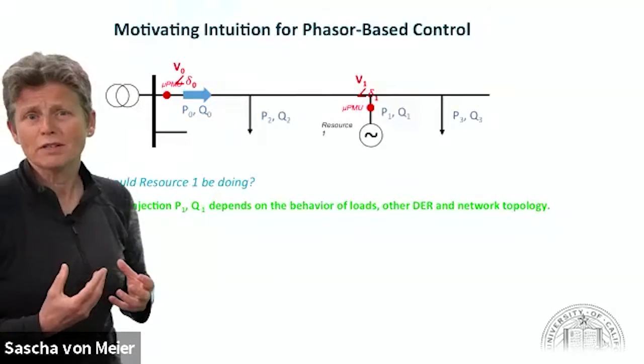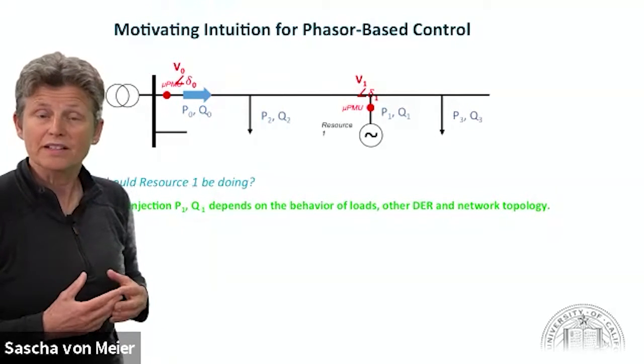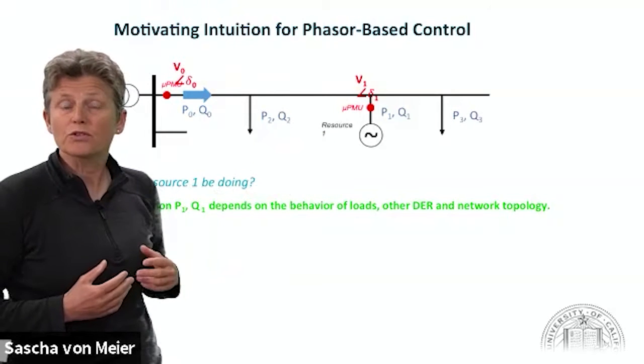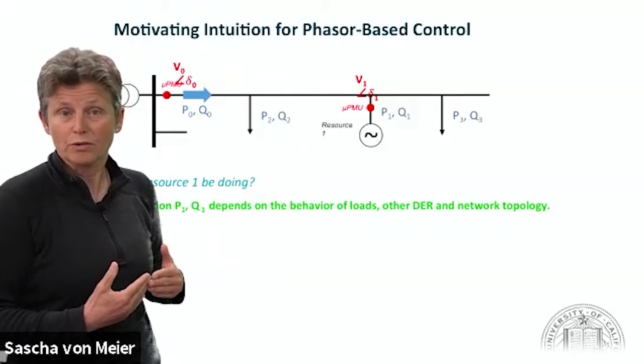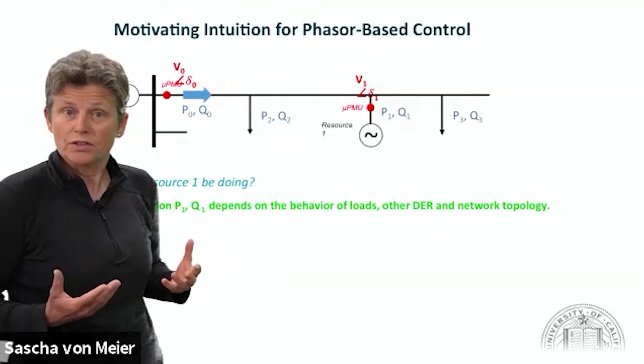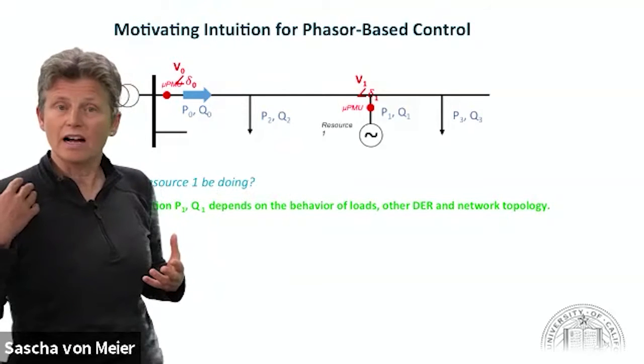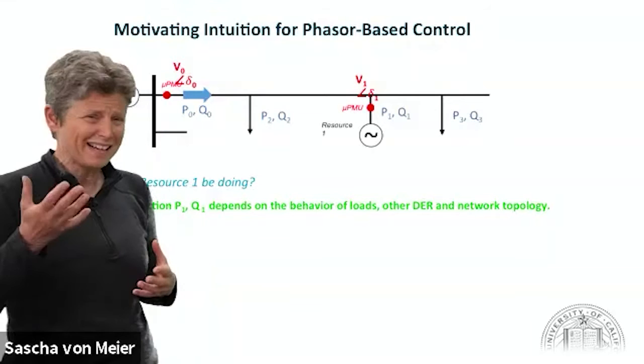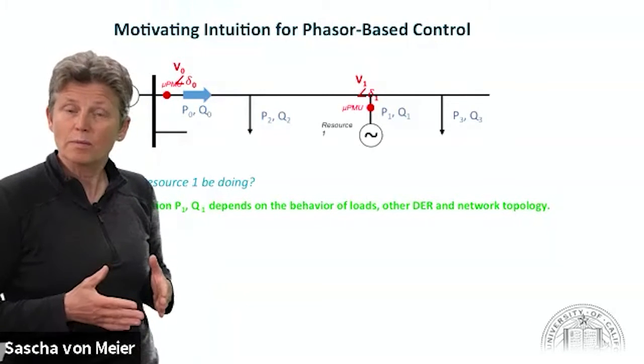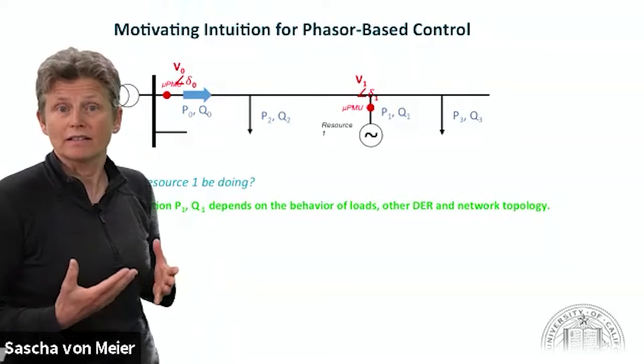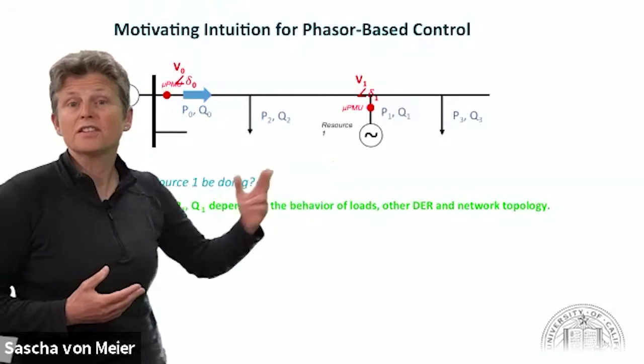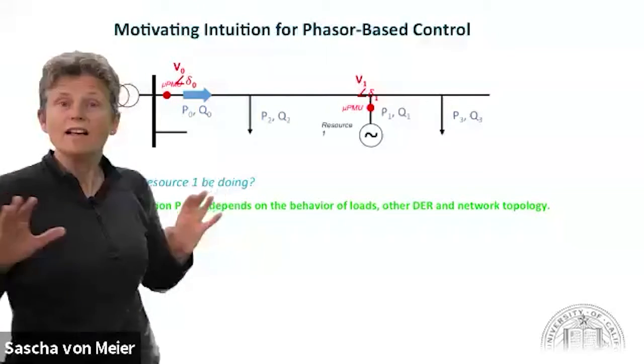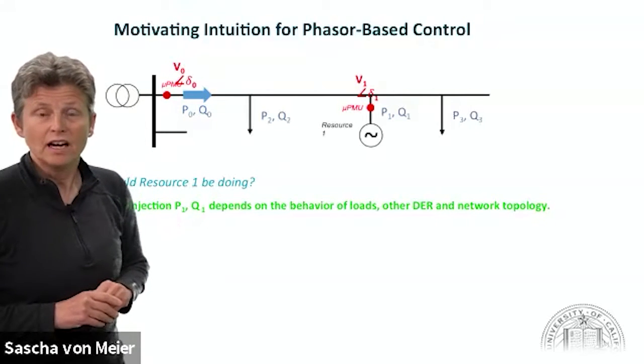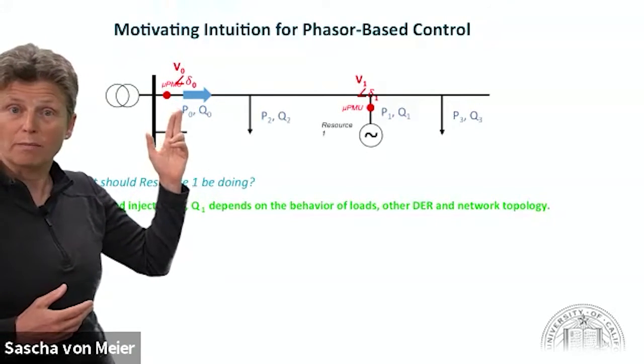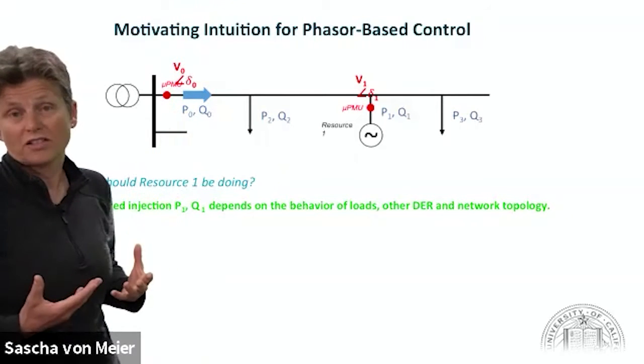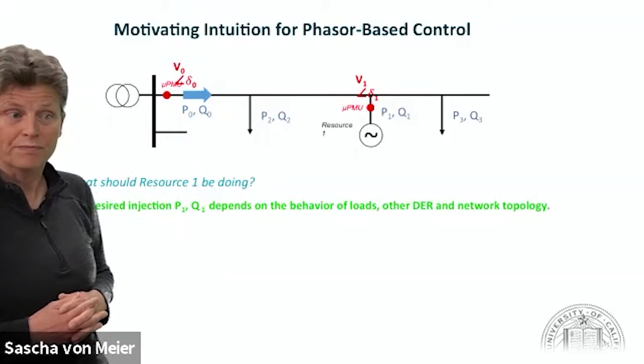But to be really responsive on a short time scale to everything that's happening, what we'd really like is for this resource to compensate for what its neighbors are doing. When there are uncontrolled solar resources—say clouds pass over the solar array—or big loads coming on, all these disturbances could be counteracted in real time by this good citizen resource that's watching what its neighbors are doing and directly compensating for it. For example, holding the power flow at the top of the distribution feeder at some constant value, or keeping it below some threshold.